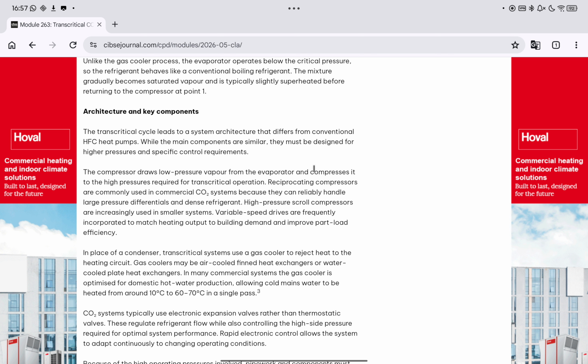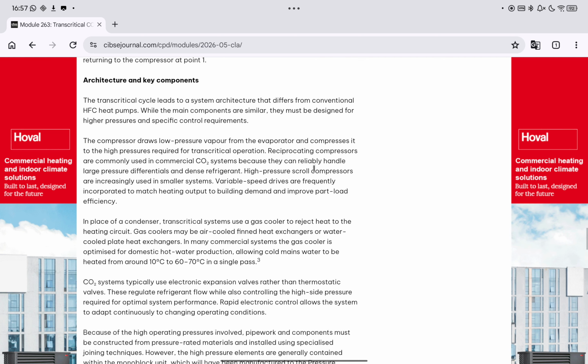In place of a condenser, transcritical systems use a gas cooler to reject heat to the heating circuit. Gas coolers may be air-cooled finned heat exchangers, or water-cooled plate heat exchangers. In many commercial systems, the gas cooler is optimized for domestic hot water production, allowing cold mains water to be heated from around 10 degrees C to 60 to 70 degrees C in a single pass.